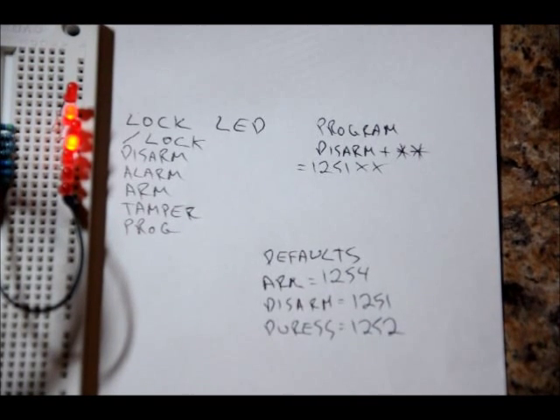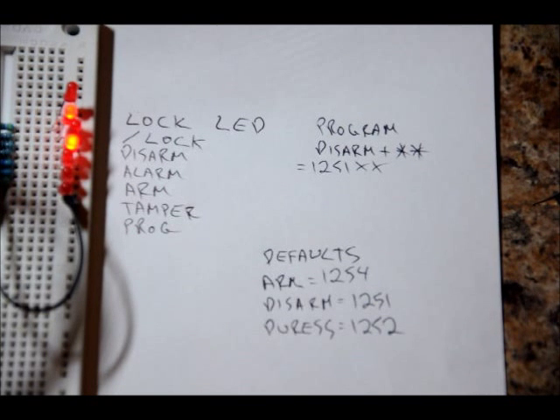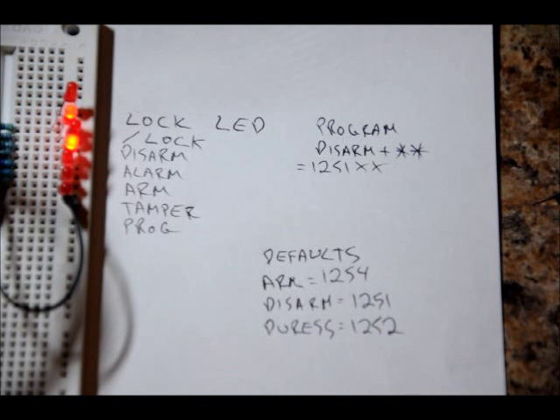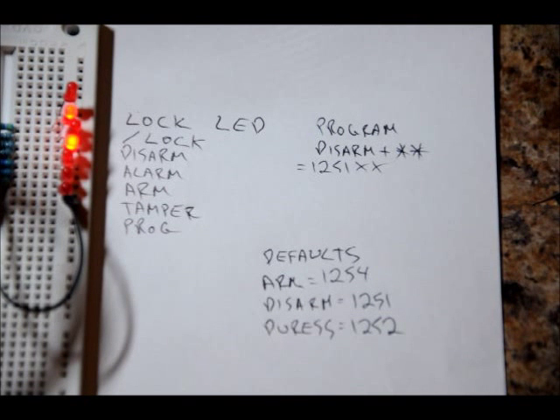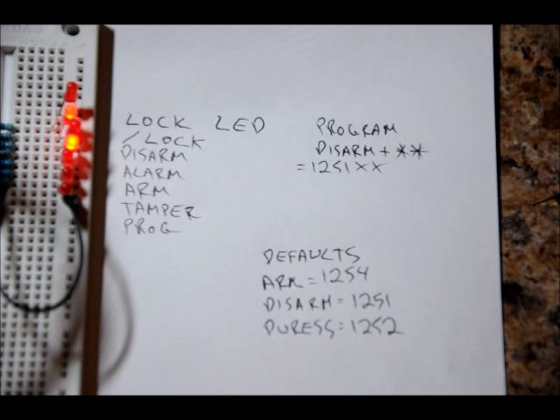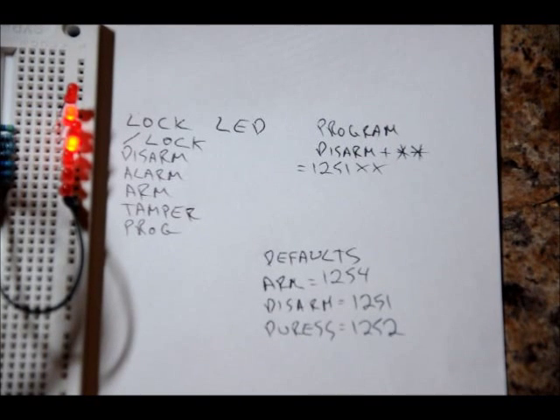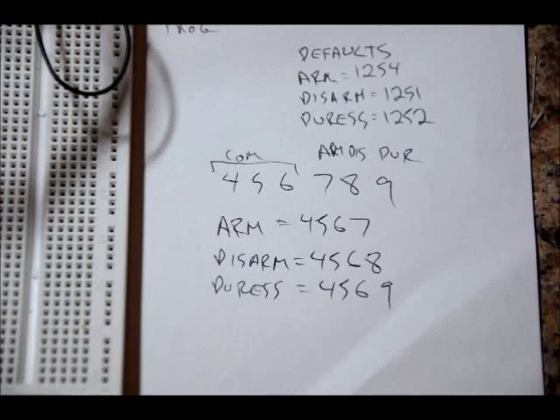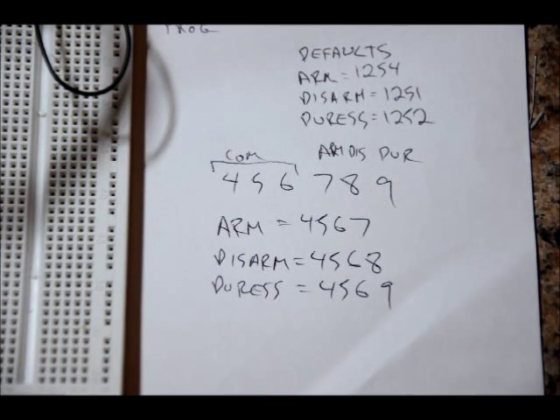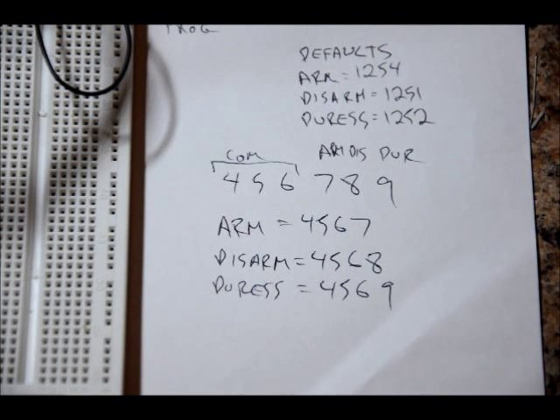What we do is we enter in six digits. The first three digits are common. The fourth digit is the final digit in the arm code. The fifth digit is the final digit on the new disarm code. And the sixth digit is the final digit in our new duress code. So that might sound a little bit ambiguous, so I'm actually going to write out an example. After we enter into program mode, the program LED will latch high. But just so you understand our new code, we enter in six numbers.